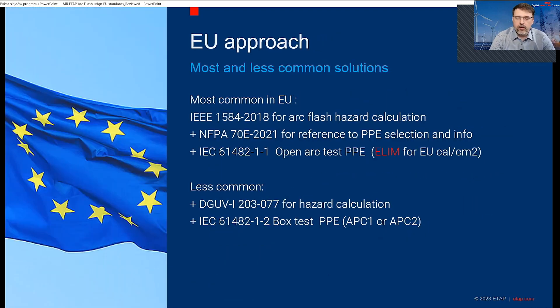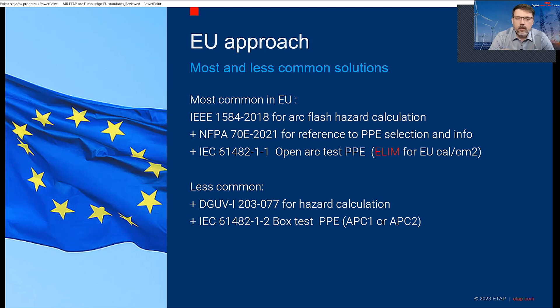So what's the approach in the EU? Actually, there are two. The first, and most common so far, is IEEE 1584-2018 for arc flash hazard calculations, then NFPA 70E 2021 release for PPE selection reference and the general way to work with results and the electrical safety plan. And then IEC 61482-1-1, which is the open arc test for PPE — specifically following ELIM (energy limit), released in 2019.